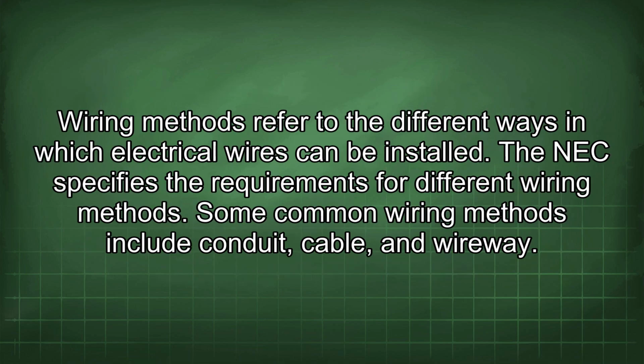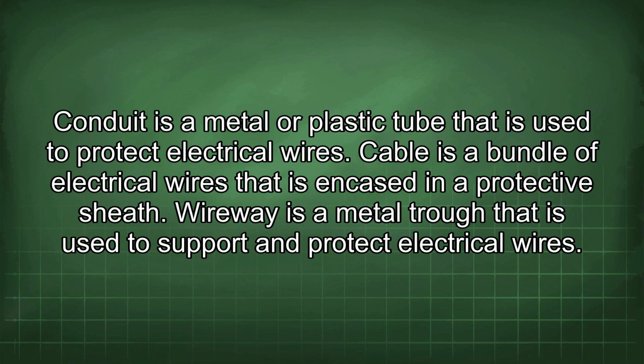Wiring methods refer to the different ways in which electrical wires can be installed. The NEC specifies the requirements for different wiring methods. Some common wiring methods include conduit, cable, and wireway. Conduit is a metal or plastic tube that is used to protect electrical wires. Cable is a bundle of electrical wires that is encased in a protective sheath. Wireway is a metal trough that is used to support and protect electrical wires.